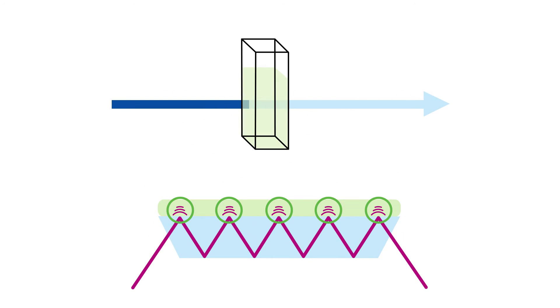In other words, the higher the number of bounces an ATR has, the larger the path length, the better sensitivity it will have.